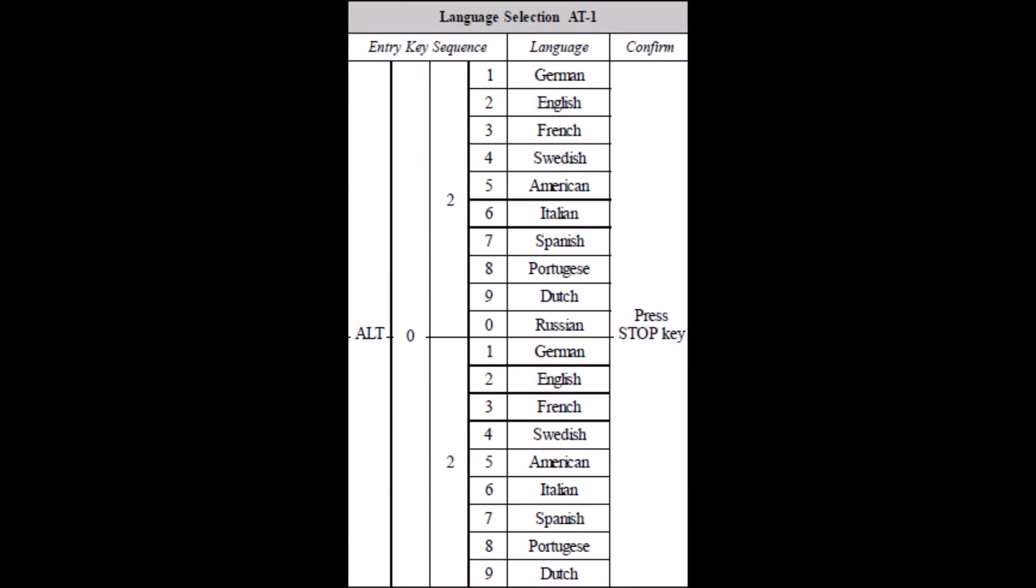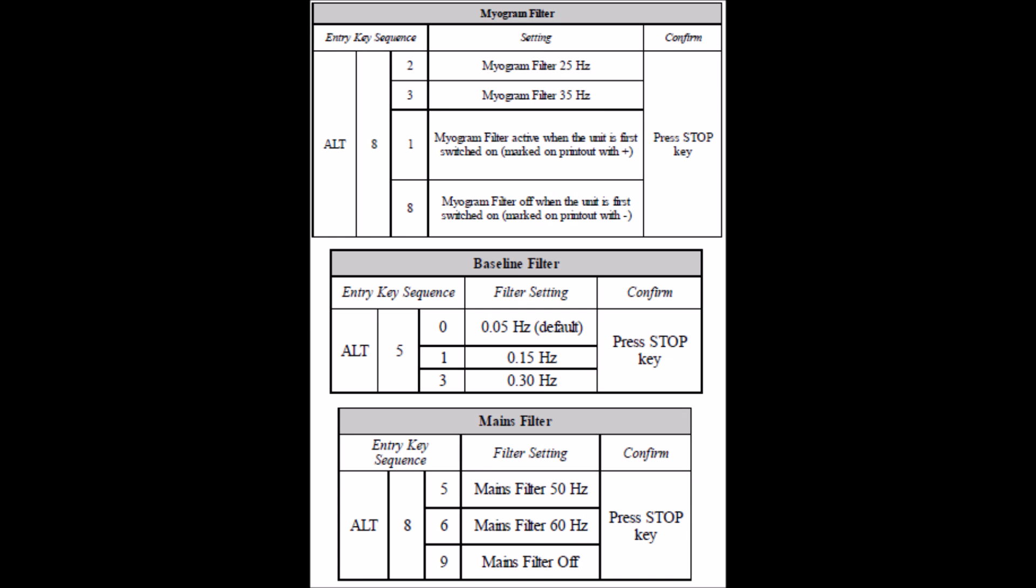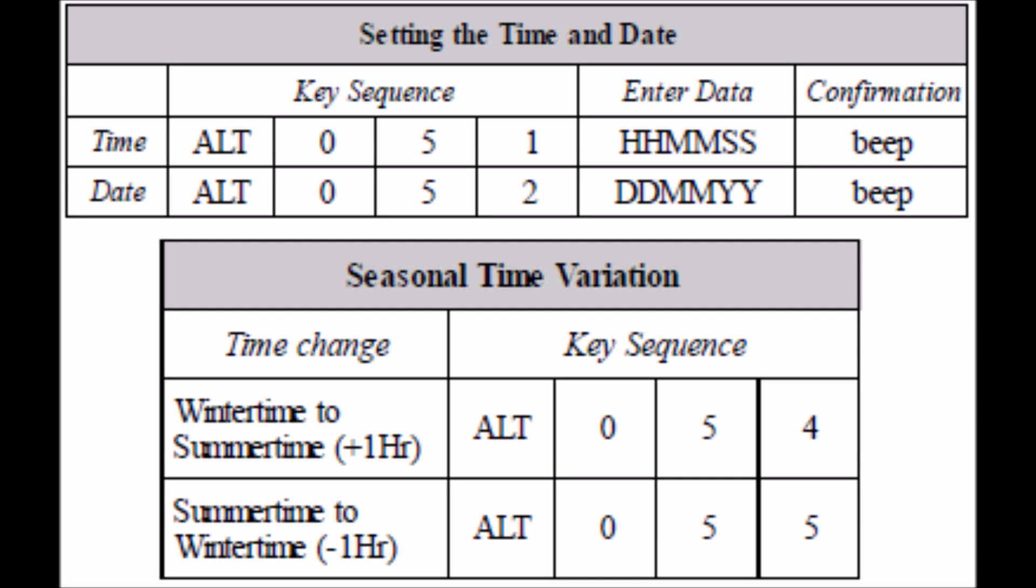To change the language setting, use the following codes. In order to change the frequencies of the myogram filter, baseline filter, and mains filter, use the following codes. If the time or date needs to be adjusted, here is the code sequence.